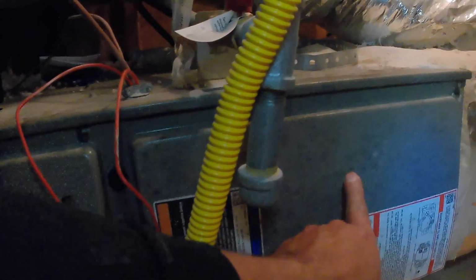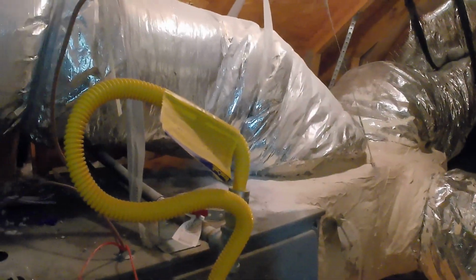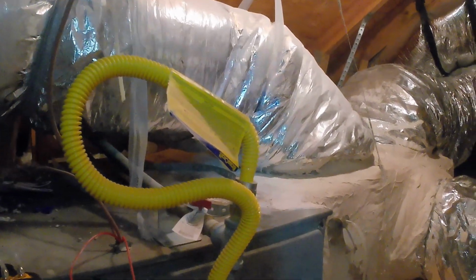The fact that it's in this unconditioned space, we can see traces of growth, so that tells me that this unit has sweat in the past, or has had problems with condensation, blocking, or a clogged condensate drain line. But I think this unit is good to go.